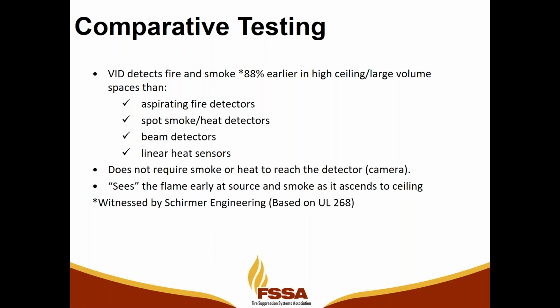So comparative testing has been accomplished using video analytics in a high ceiling application, tested against aspiration detection, and spot detectors and linear detectors. We don't see video analytics as a competitor of aspirating fire detection. If it's a high ceiling application, it makes sense for video analytics, because video analytics can analyze the image floor to ceiling, detect the smoke as it is rising, and alarm way below the ceiling. In high airflow spaces, we don't use video analytics, because the smoke will be broken up or removed from the space altogether, and we won't be able to detect it.